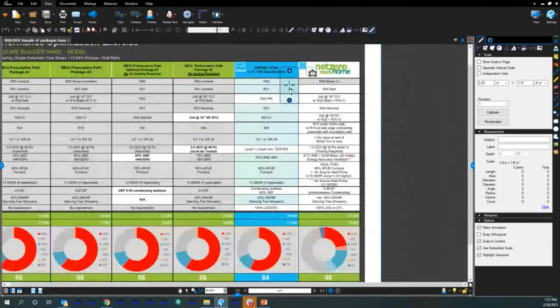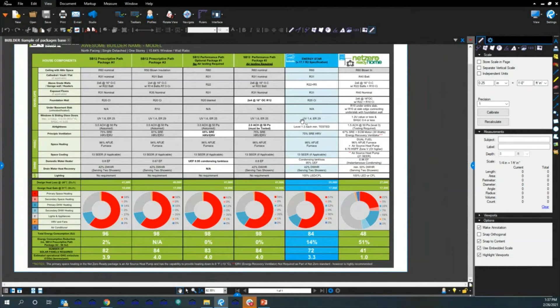Generally I would not need to model this, that would just be the prescriptive path. However, I did it for this exercise, and you can see it was 84 gigajoules, about 14% better than A3. In general, Energy Star is 15 to 20% better than code. It's arguable what the word code means, that could be A1, A3, you know, but generally it's about 15 to 20%.